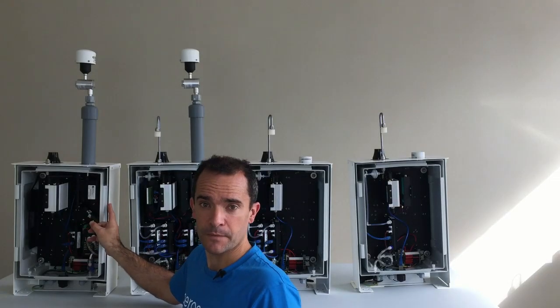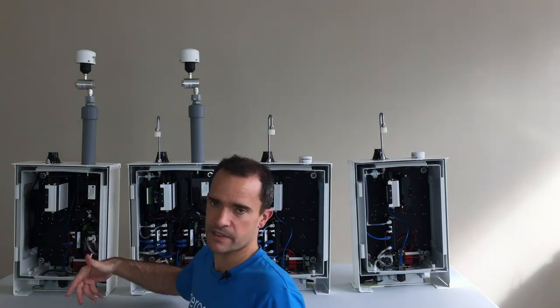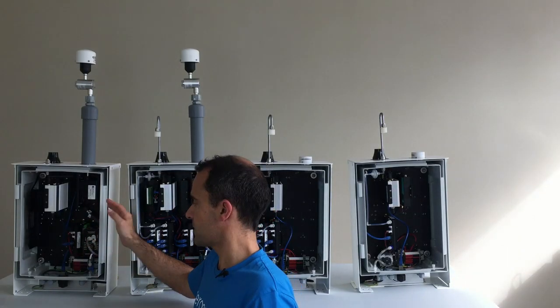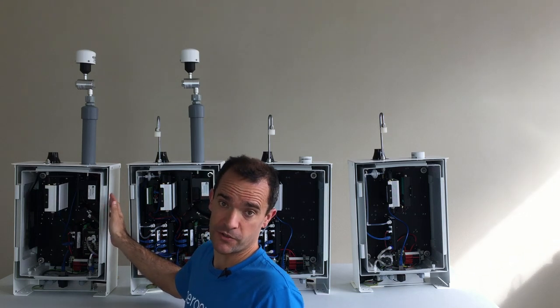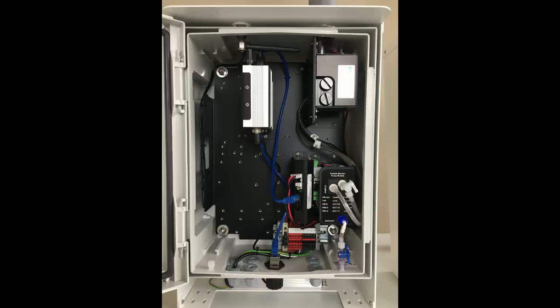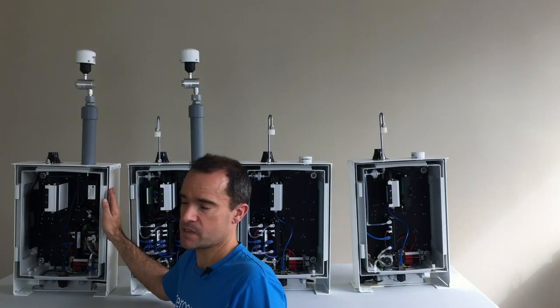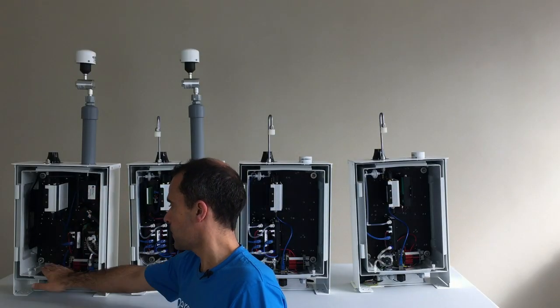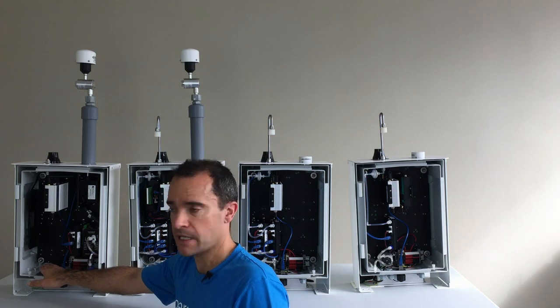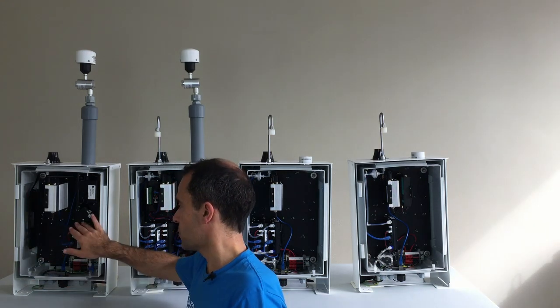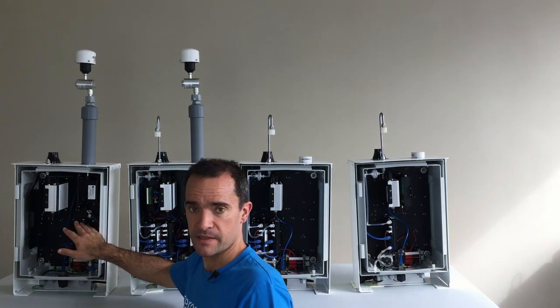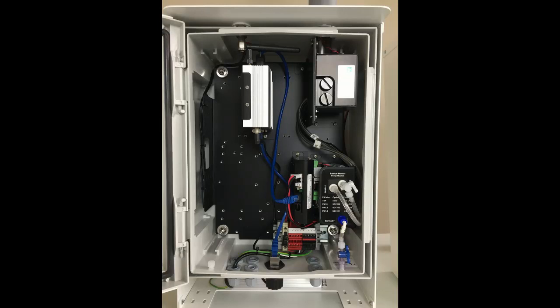And finally here we actually have an AQS1 which is configured with PM only. This is very similar to our standard Dust Sentry, it doesn't have any gas sampling. But as you can see it does have a gas sampling inlet ready to be attached. So you can order the AQS1 with PM only. You can see there's no pump module down here, there's no inlet filter. We just have the PM sampling system and we have plenty of space to add gas modules later if you need to.